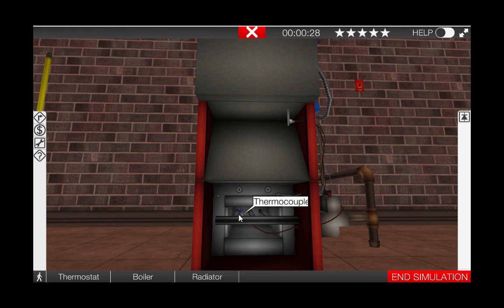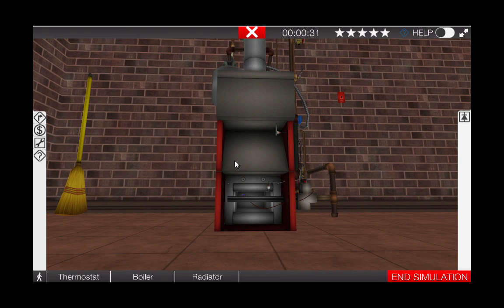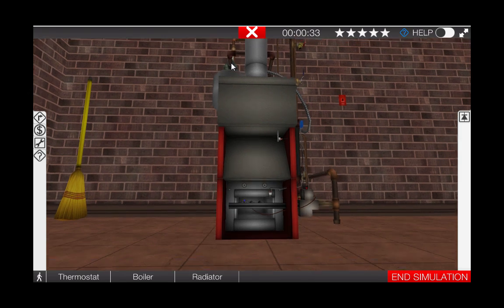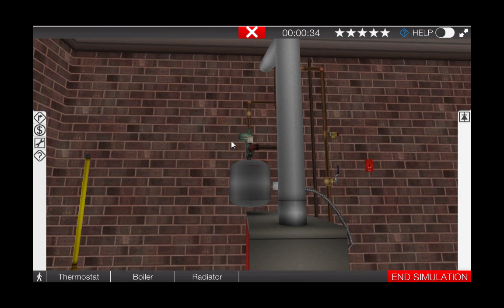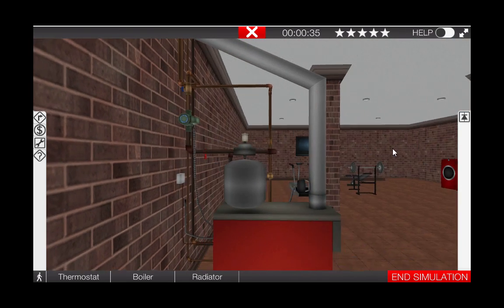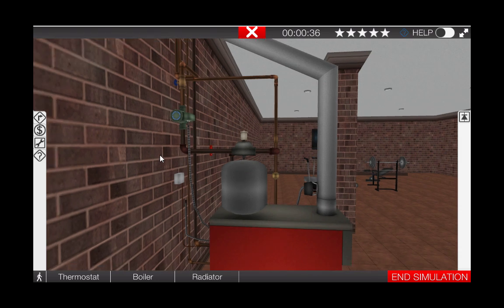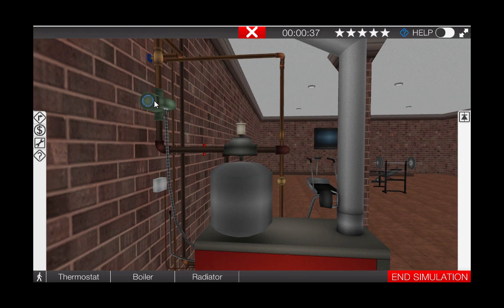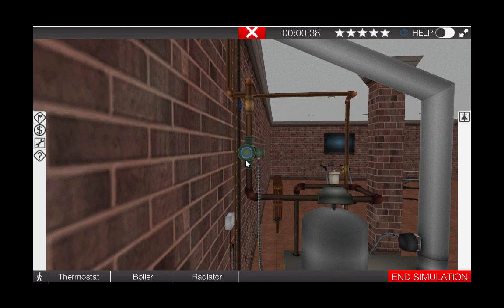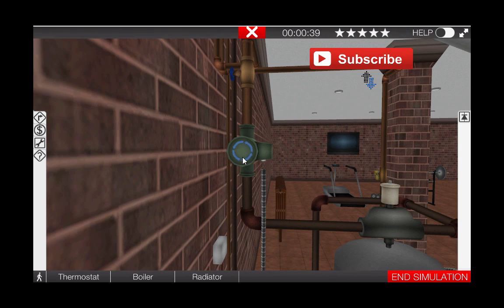Next we want to see if the circulator pump is running. Right click the circulator to center it in your field of view and zoom in. You can see from the graphic that the circulator is operational. This means that we have a problem with the burner circuit.